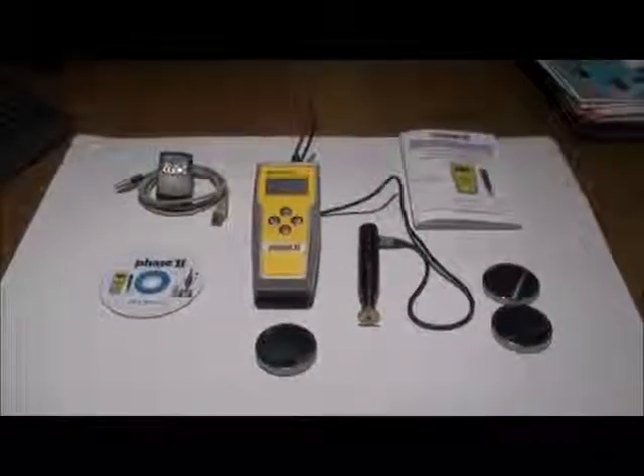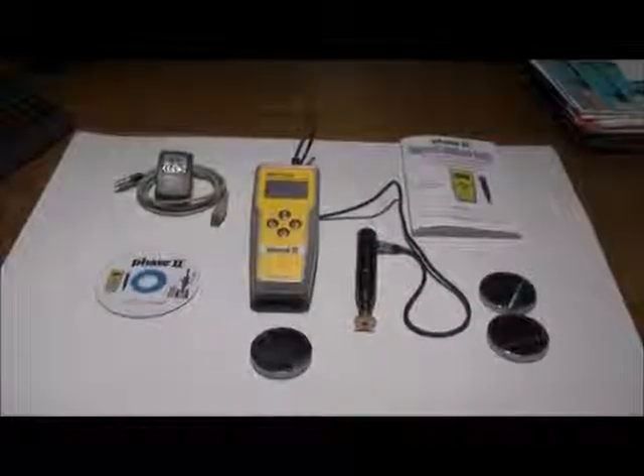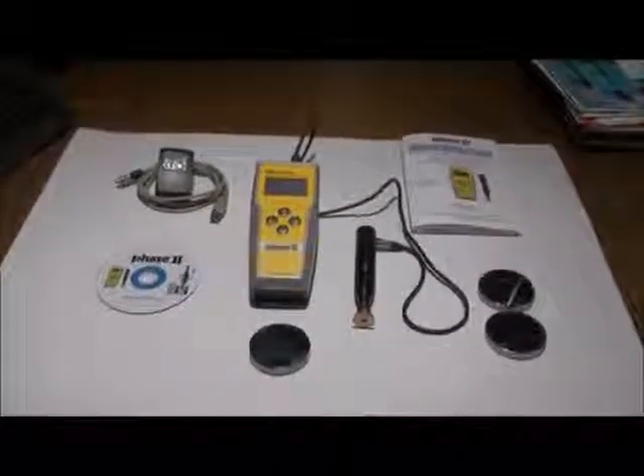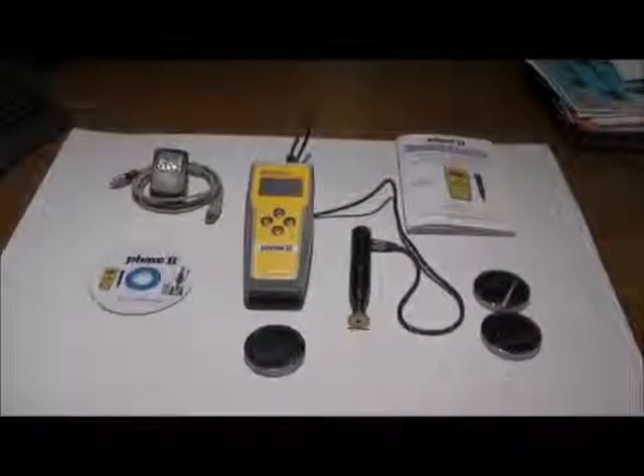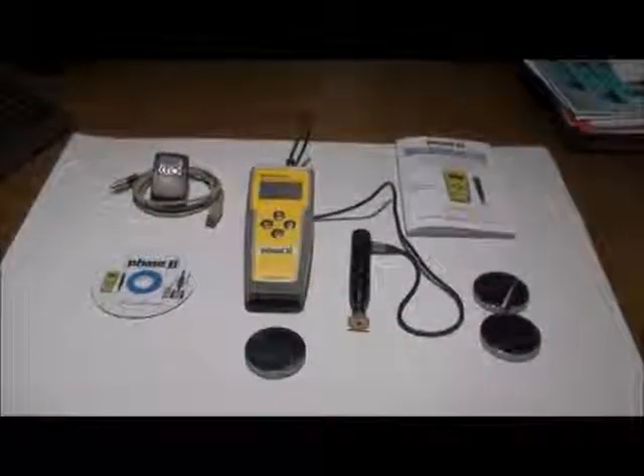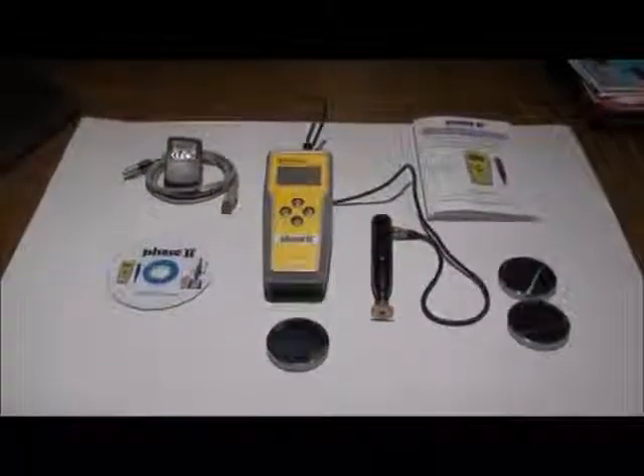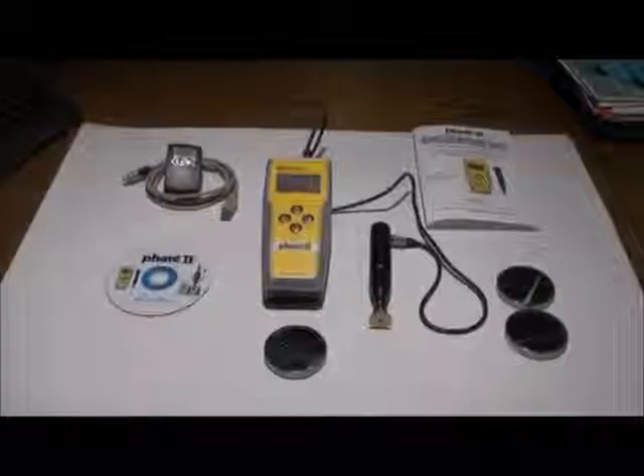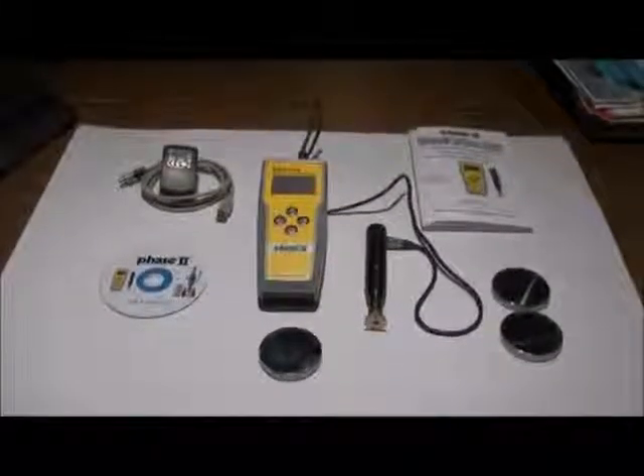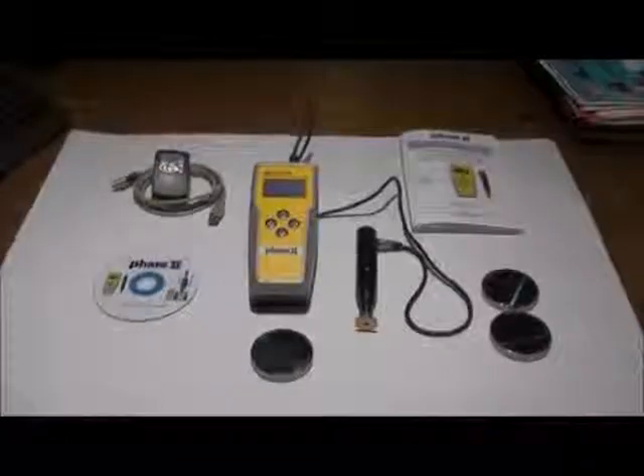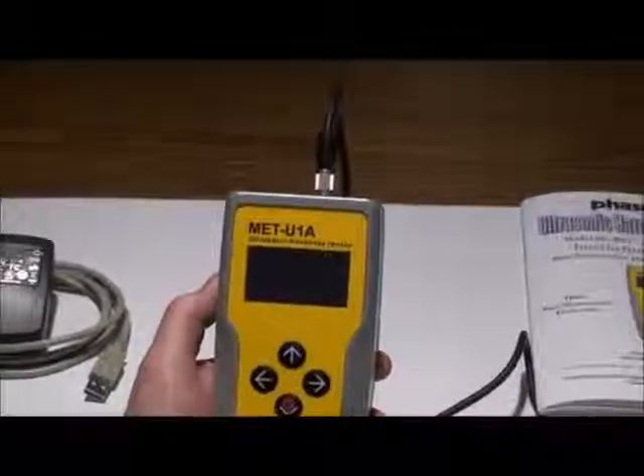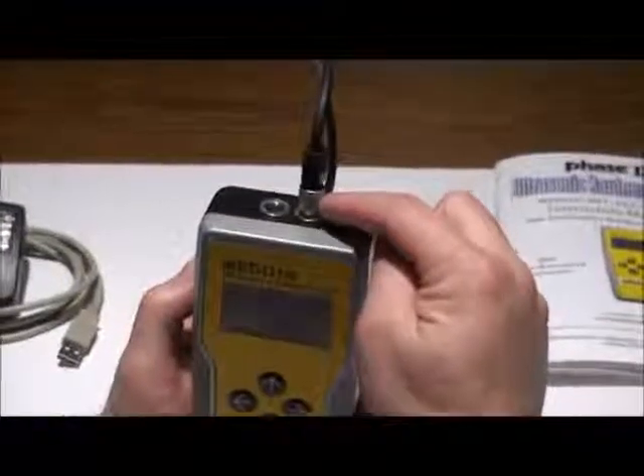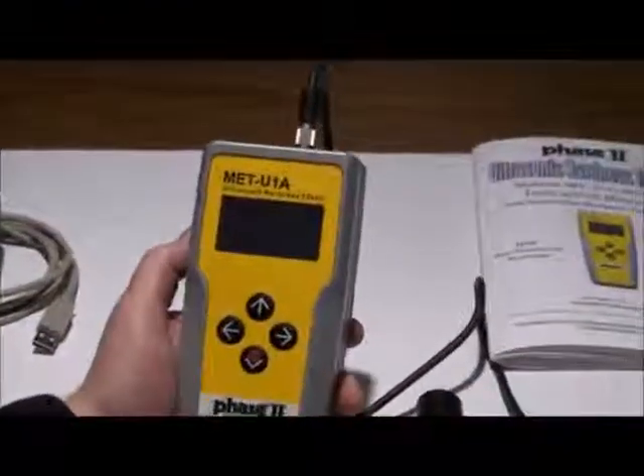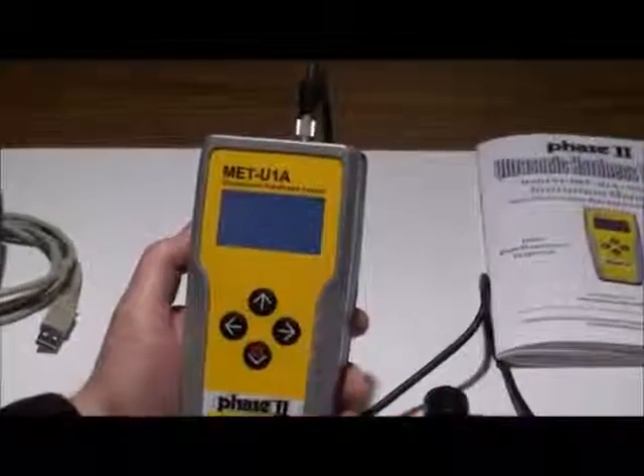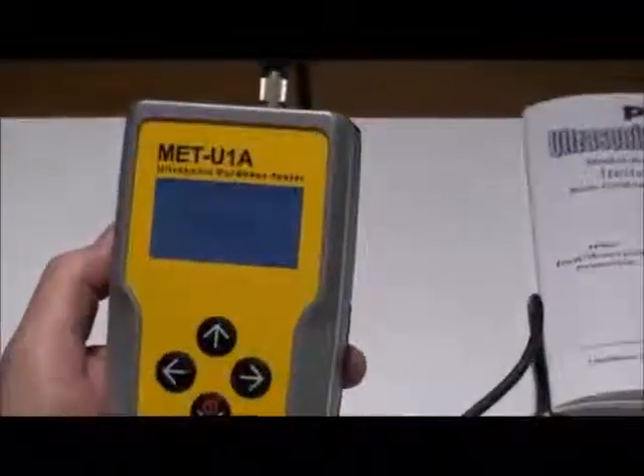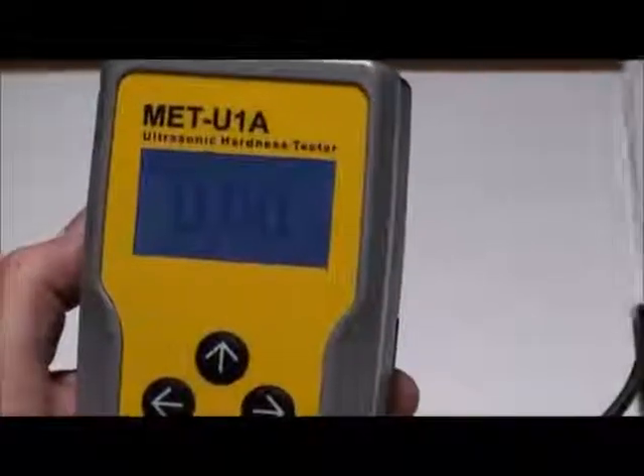To clarify which model has which probe, the MET U1A uses the 1.5 kilogram probe, while the MET U1A 50 uses the 5 kilogram probe. Now let's move over to the operation of the hardness tester and see how easy it is to utilize the different functions, taking tests, and obtaining results. To begin, insert the plug of the probe into the correct socket on the tester, carefully threading down. Press the bottom arrow on the tester to power up. The screen will show connecting sensor, then recognize the sensor being used, in this case ultrasonic sensor.